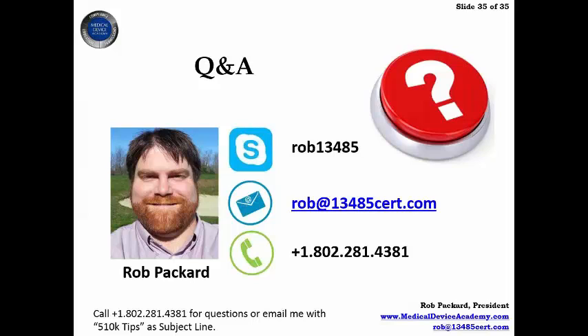When you run into challenges is when, let's say you have 4 different functions, 4 different components, and 3 out of the 4 have a predicate. That's when you need somebody's help. And I'm actually working on one of those now where 3 of the components are definitely a great candidate for a 510K and have a pretty logical 510K predicate. But the 4th one is out there, and we might have to do a de novo for it, or we might even have to do a PMA. And so the question is, do we keep that functionality out, do an initial submission of a 510K with the 3 functions, and then add on the 4th function as a version 2 of the product? So that might be one of the strategies we go with that product.